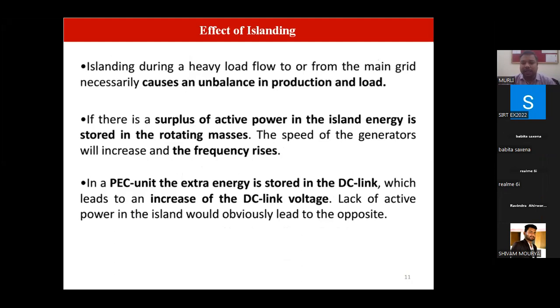Because unintentional islanding must be detected, as there can be a hazard to the personnel working there. If the microgrid was operating with the grid and suddenly it is disconnected, this kind of scenario is not healthy for the equipment and for the personnel who are operating it. So for both cases, it is not expected. The effect of islanding is to cause unbalance in the production and the load, and a frequency mismatch also arises due to this. So for that reason, islanding should be detected on time.